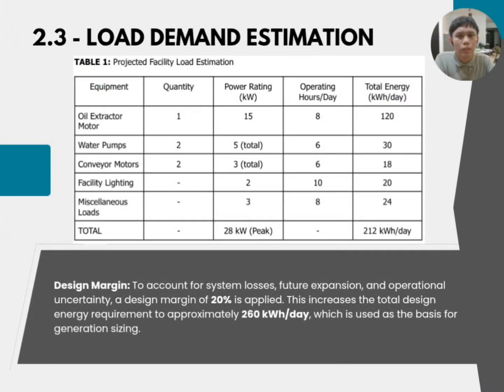Alright, we are now at slide 2.3, where we are going to talk about the load demand estimation. Here, we are going to discuss the estimation made for the facility. The facility has a peak load of 28 kilowatts with a daily energy consumption of 212 kilowatt hours per day. And for the design margin, we applied it to account for system losses, future expansion, and operational uncertainty.